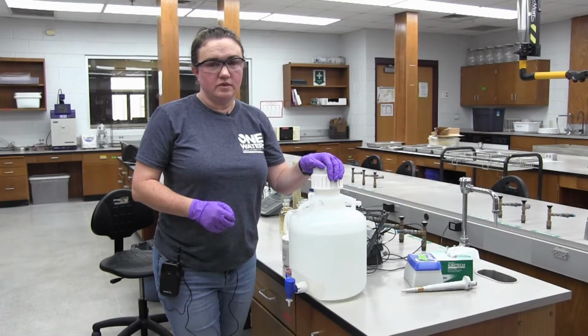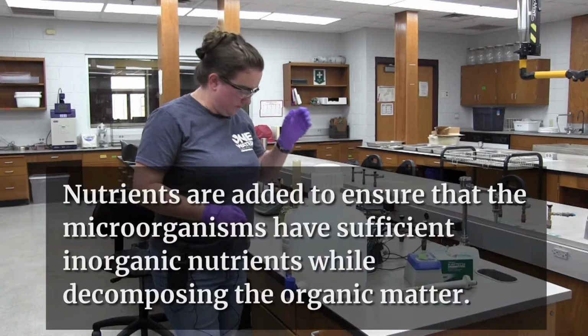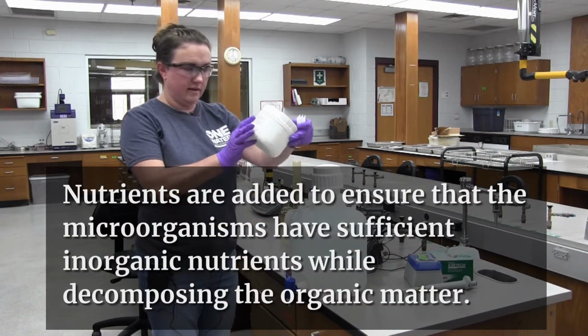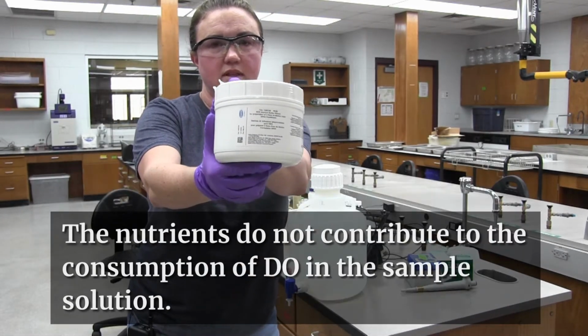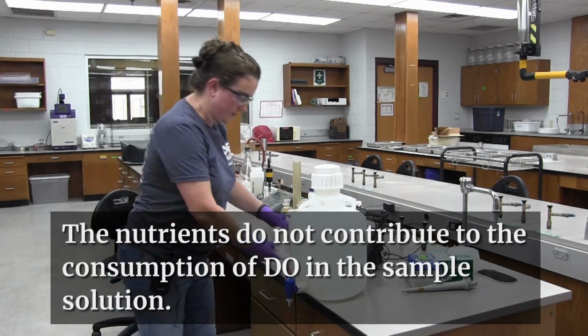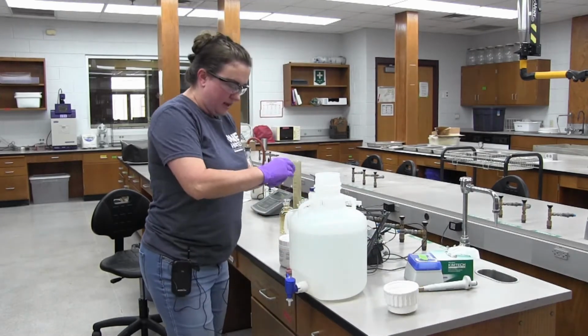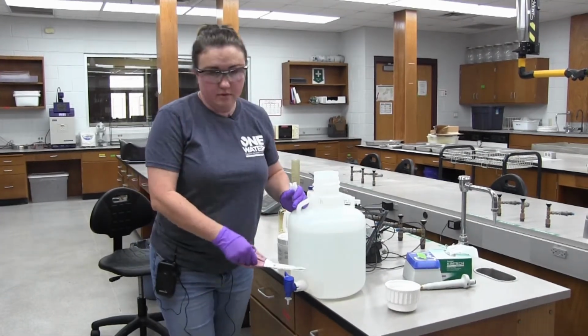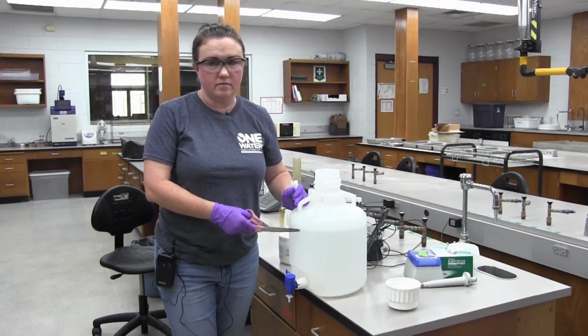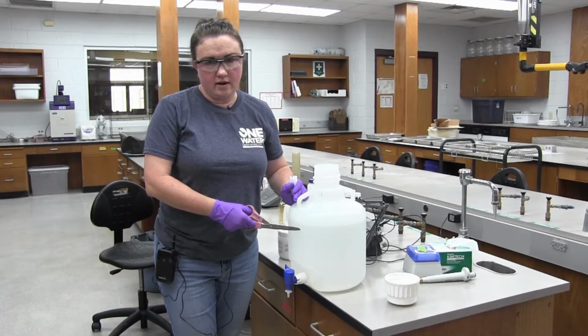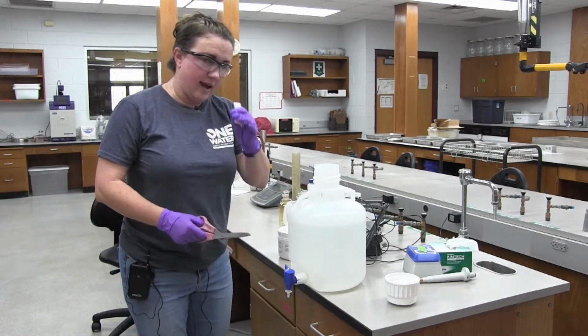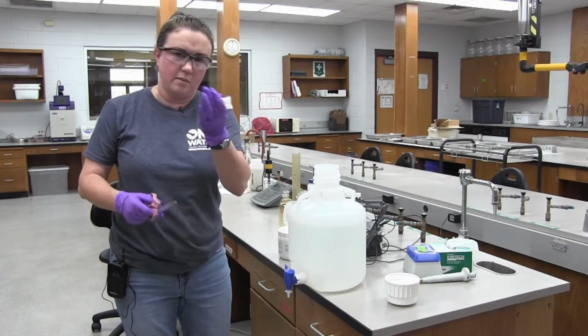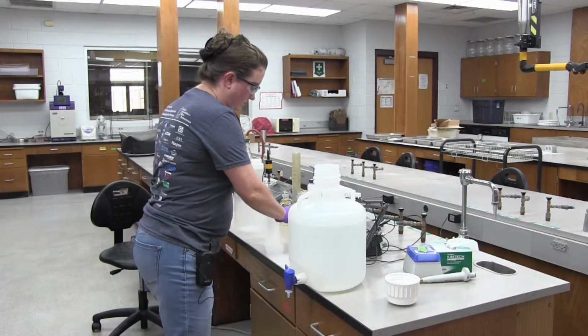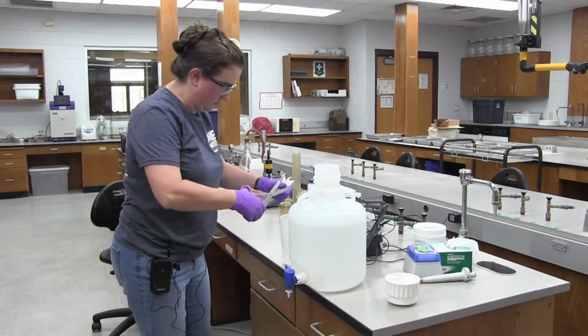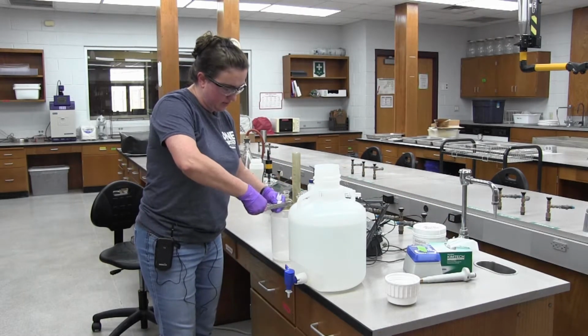For the BOD test, we will need to make up some nutrient buffer water. We do this by adding some BOD nutrient buffer pillows. This will give the bugs some nutrients while they're consuming the oxygen. Okay. And this is just DI water that has been aging in the 20-degree incubator for at least a week, and we're going to add these buffer pillows to it. You might want to shake them up a little bit to mix them, and just take some scissors and cut off the tops.